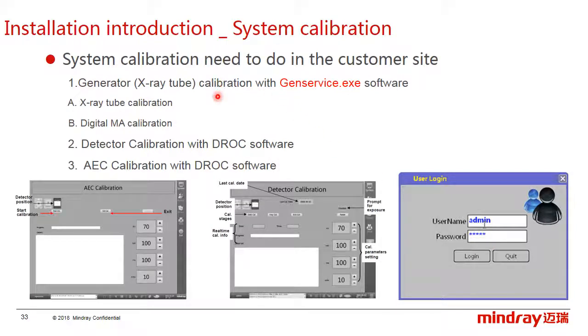Mechanical installation. Some system calibration needs to be performed. Generator calibration, including the X-ray tube calibration, also called tube training, and digital mA calibration. The generator calibration needs to be performed in the gen service. Besides, detector calibration, which is performed in the DROC, and if AEC was configured, AEC calibration is required. We will learn the calibration in the installation part.